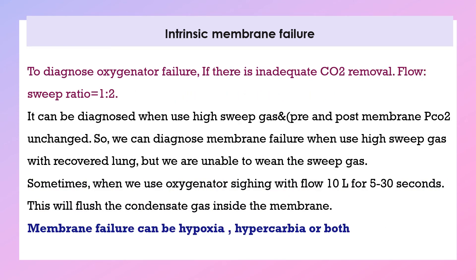Another form of oxygenator failure is inadequate CO2 removal. It is diagnosed when using high sweep gas, pre- and post-membrane CO2 is unchanged, or when the lung has recovered but weaning off sweep gas is not possible. Using a sigh breath with flow of 10 liters for 5–30 seconds can flush condensate gas inside the membrane. Membrane failure can present as hypoxia, hypercarbia, or both.